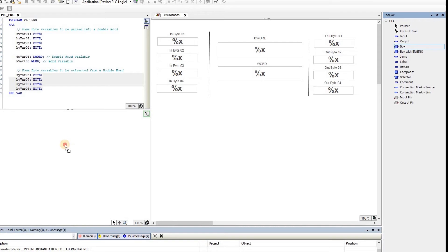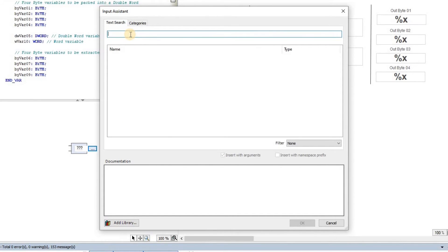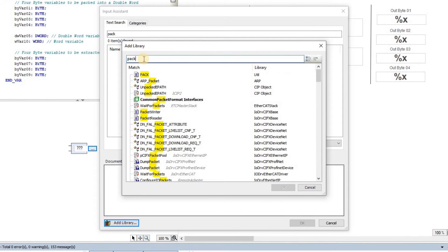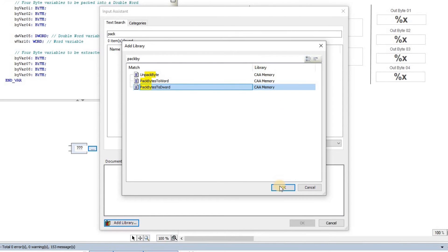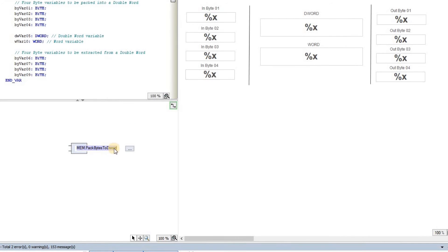I drag and drop a box from the toolbox into the program area, then look for the function we discussed. Initially if I type 'pack' nothing appears, which means we need to add the CAA library to our project as it's not already there. Once I add it and type 'pack' again, all functions including pack will appear. I find Pack Bytes to Double Word, which is in the CAA Memory library. Clicking OK adds the library to the project, and I can now choose that function.